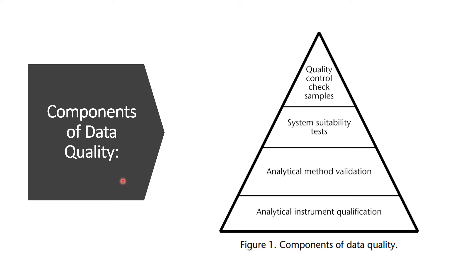Now in this slide, we will discuss the components of data quality. In USP Chapter 1058, it is mentioned how the components of data quality should be structured, which you can understand easily with this pyramid. First, you will procure the instrument and perform the qualification activity to ensure the system performance is satisfactory and the system is fit for the intended use. Use of a qualified instrument in analysis contributes to confidence that the validity of generated data is of high quality.